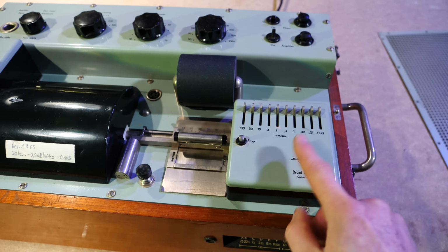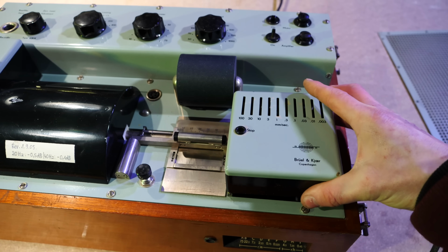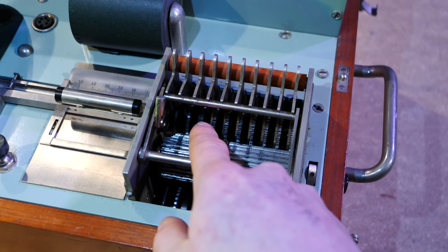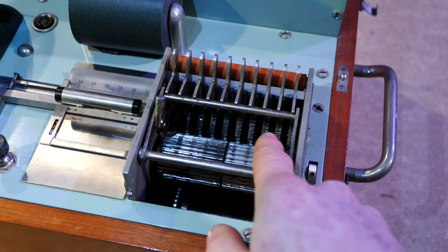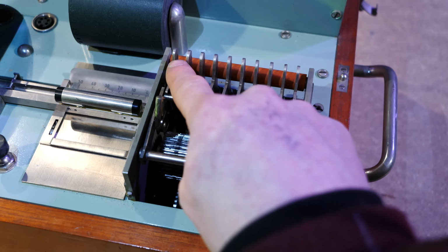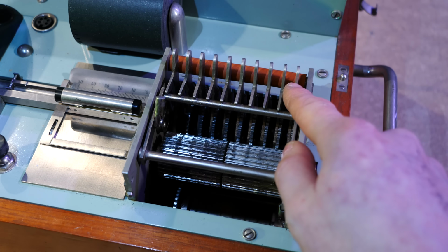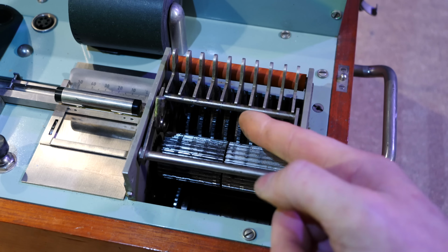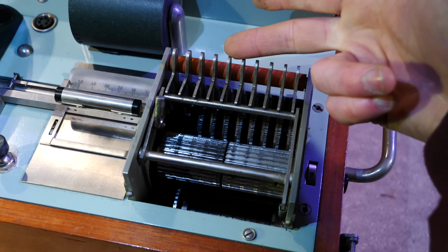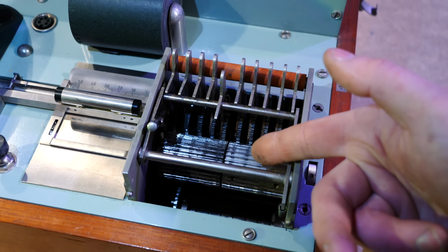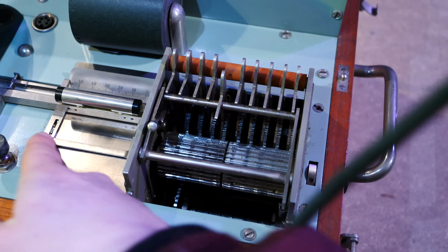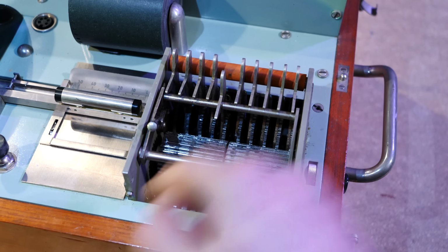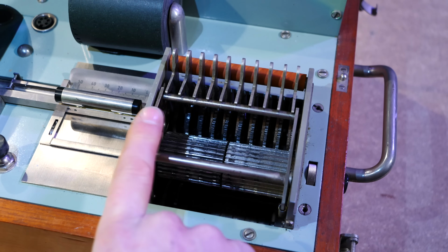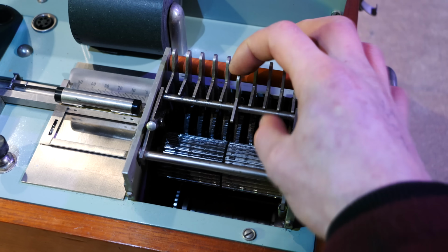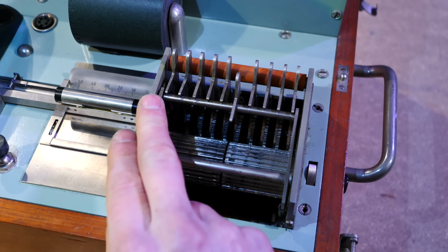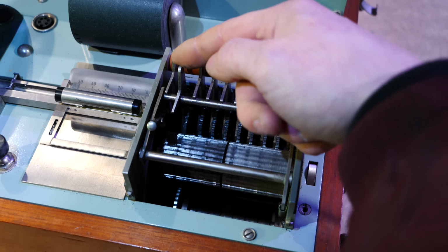How this works is really cool, and we've got to have a closer look at that. So you'll see at the back there are reduction gears that are basically reducing the further you go along, all the way up to the slowest, which is right here, from 100 millimeters a second all the way over to 0.003 millimeters a second. And how you engage these is amazingly simple. You just put it in and it connects up to this drive cog, which is connected basically to the drive shaft of these teeth right here. And to disengage, you push this and it basically lifts this up and disengages this part, which makes it spring back into place. But just how cool is that?